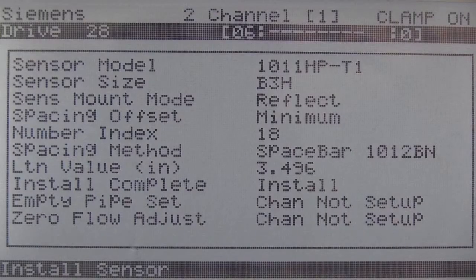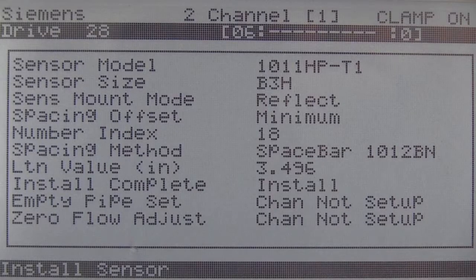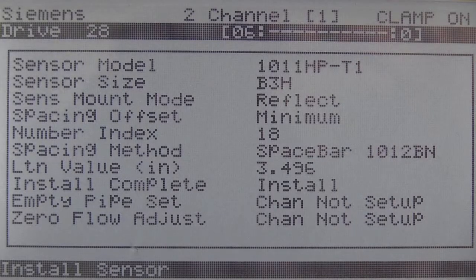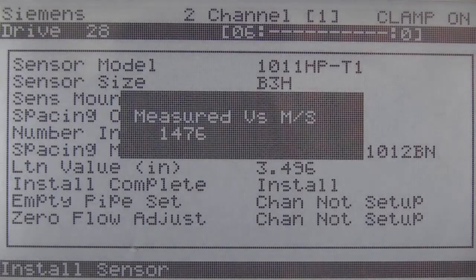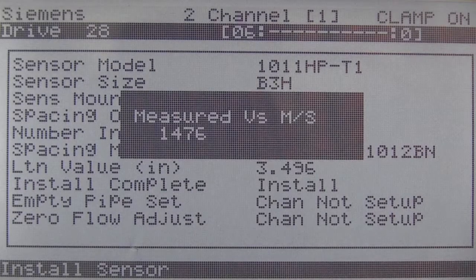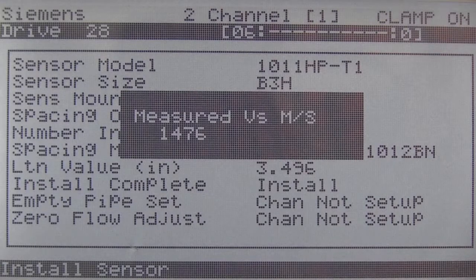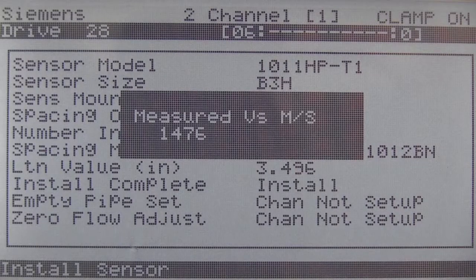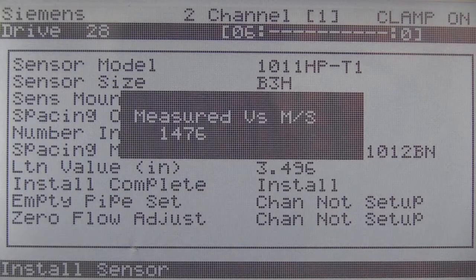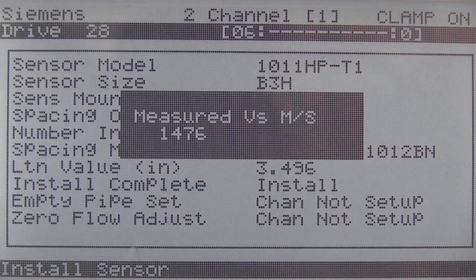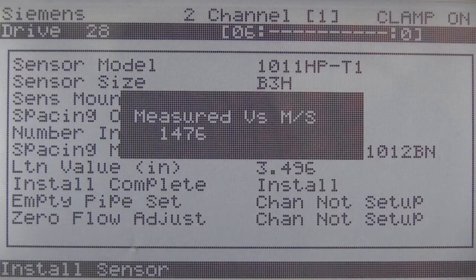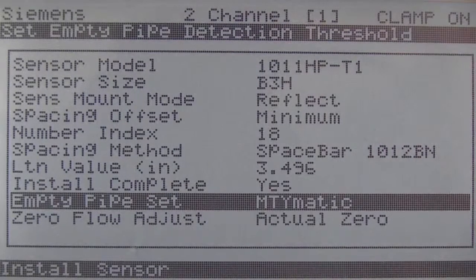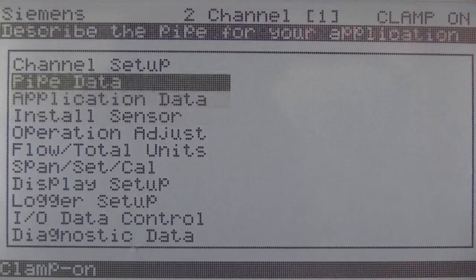Evaluation of your meter operation begins once it is successfully installed. We accomplished this when we saw the meter publish your liquid sonic velocity, VS, during the installation procedure. VS is an extremely important indicator of meter performance that I will be emphasizing as we proceed. But first, we just want to initiate operation so we can simply press the down arrow to proceed. From here, it's just a few keystrokes to access the diagnostic menu.